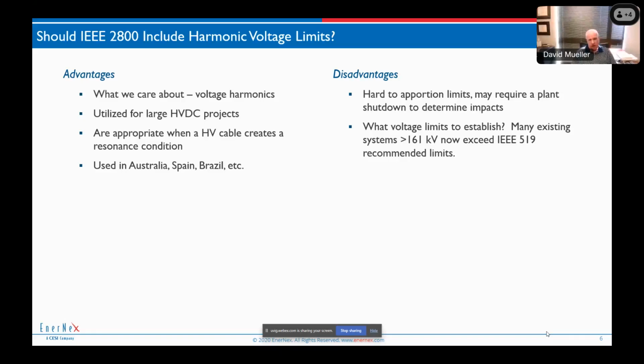But there are some problems with harmonic voltage limits. First of all, it's hard to determine what a plant would cause in harmonic voltage distortion. If we're below the limits, then we're fine. But what if the system is already above the limits? And that is the case. I'll talk about this a little bit more later, but many of our systems in the US currently exceed the IEEE 519 recommendation for harmonic voltages, particularly 230 and 345 kV high voltage systems, which exceed the 1.5% and the 1% limit.